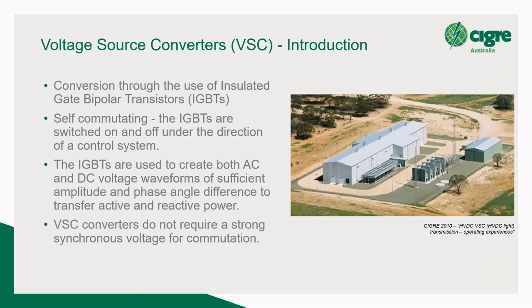But of course, with VSC converters, there is still a lower limit as to how weak the network can be and for it to meet the normal generator performance standard requirements. So yes, it will work, but will it meet all the requirements of your grid connection, and how low can that system strength or short circuit ratio be?